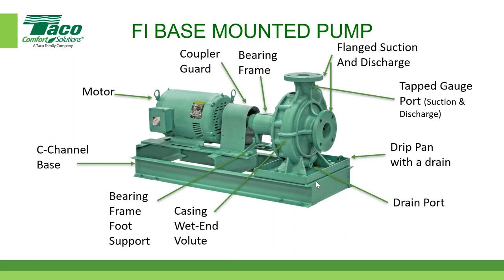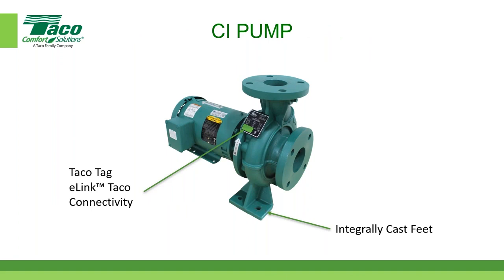And this is known as a split-coupled pump because there are two shafts, the motor shaft and the impeller shaft. All right, that's pretty common. And I'm sure many of you know other manufacturers' models have many of these same components, right? There's always a little difference, but nonetheless, they have many of the same components. Here's the CI pump. So this is a direct coupled, okay? So you can kind of see the difference there. The motor shaft is the impeller shaft.